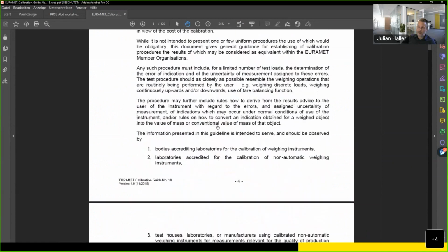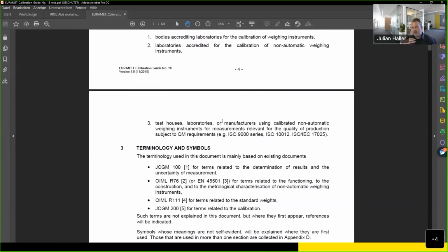But for OIML, I do know that it is quite common all over the world to calibrate according to OIML R76. I do not recommend that, because R76 does not give any uncertainty calculation guidance. From my perspective, R76 is really a testing procedure for legal metrology, and cg-18 is a calibration procedure, and we really distinguish that. If we do legal metrology measurements, we do that according to R76 and test against the respective MPEs. But if we calibrate, we calibrate according to cg-18.